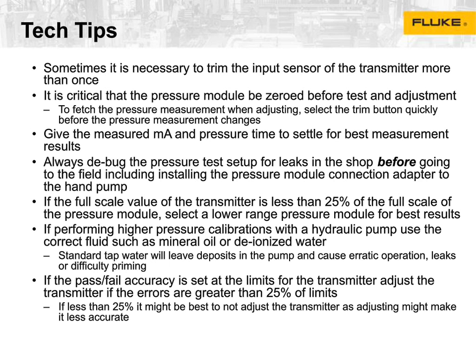Last but not least, or actually I guess I'm going to talk about these together. If the full scale value of the transmitter is less than 25% of the full scale value of the module, select a lower pressure module. What that's basically saying is that if you are at the low end of the range, go get a lower end pressure module. If you are using a 754, similar to gauges, you need to have pressure modules that fit the work that you're doing. What we frequently see is that people will use a pressure module for most of their work, and then maybe use a gauge for something lower down, and then document the calibration manually. If you have to have the documenting feature, you can get another pressure module.